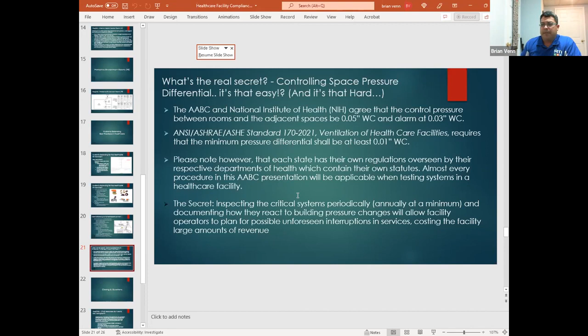So I say to the TAB people, in a healthcare environment, anything that could possibly be wrong with the room that isn't allowing you to achieve your pressures is an item to be documented. Because we are trying to reach this 0.05 that AABC and the National Institute of Health now agree is a good control space, adjacent space pressure to achieve.